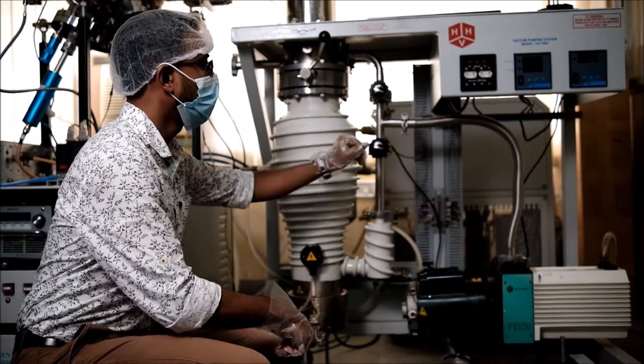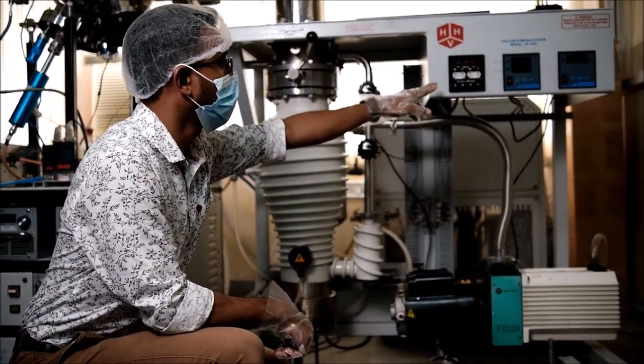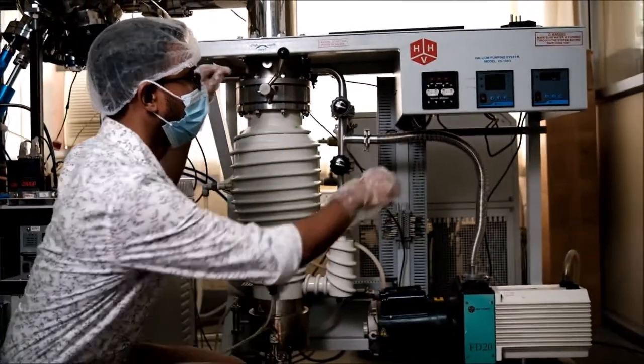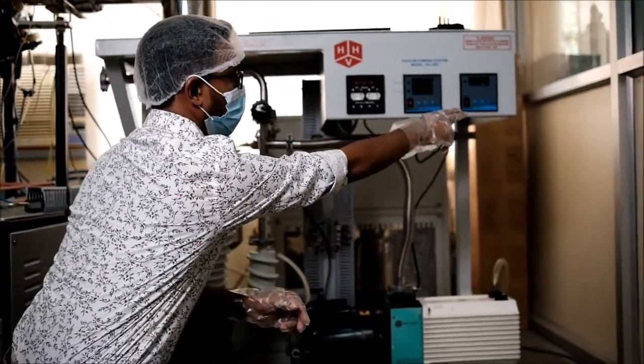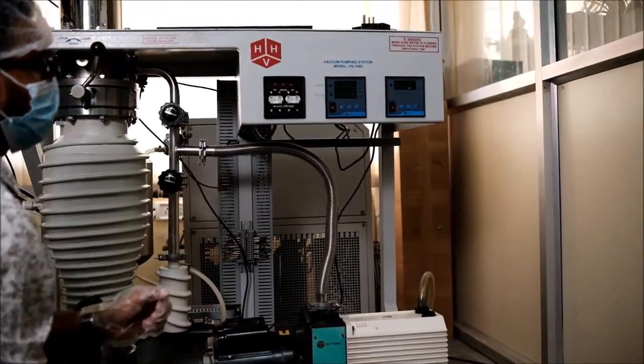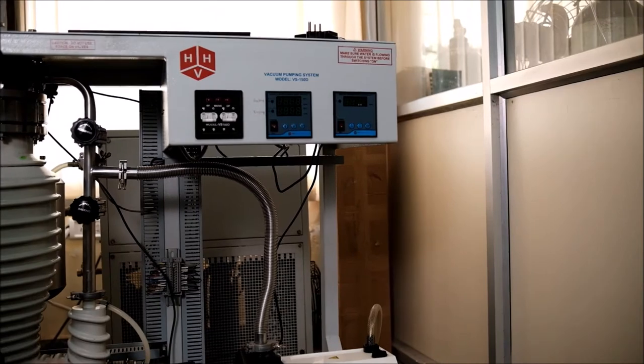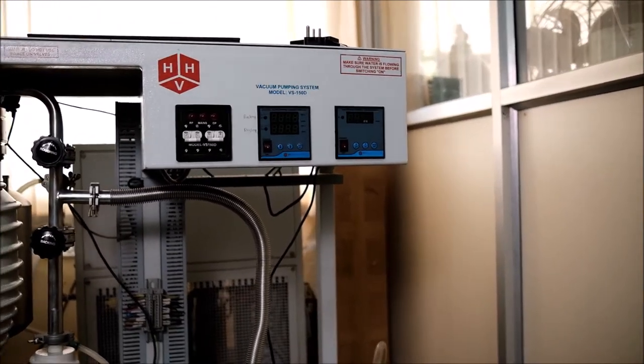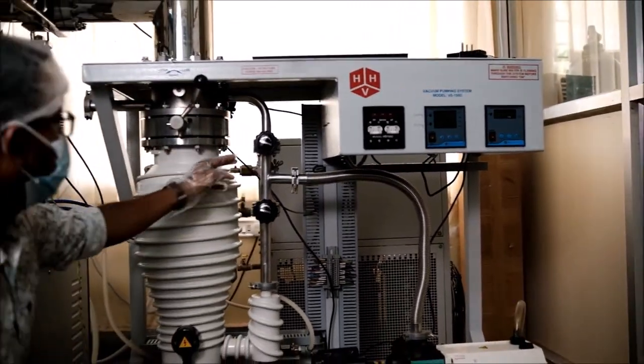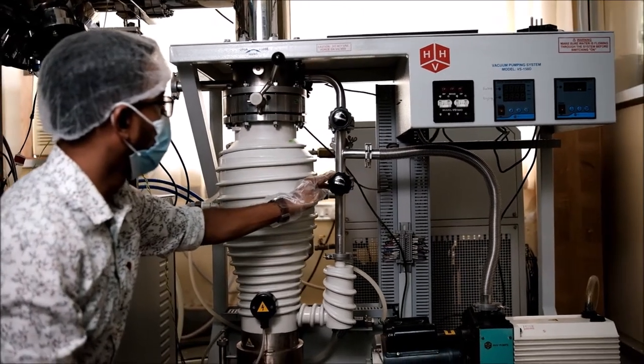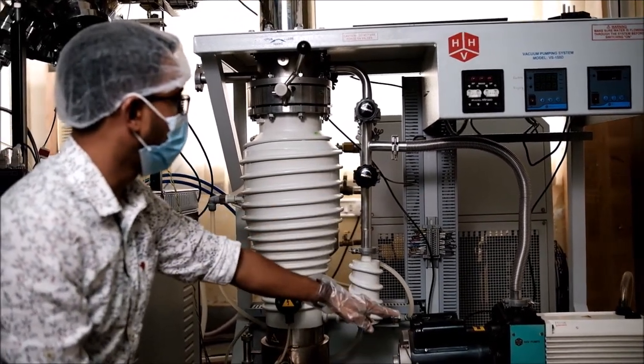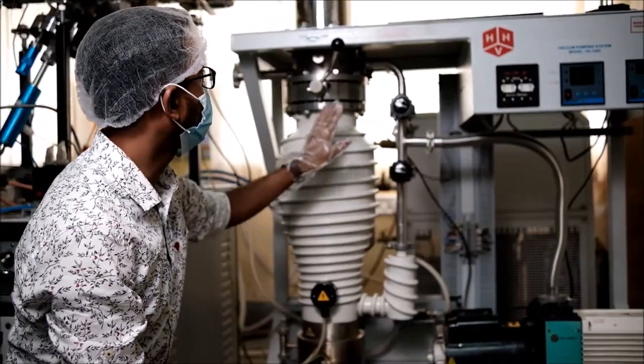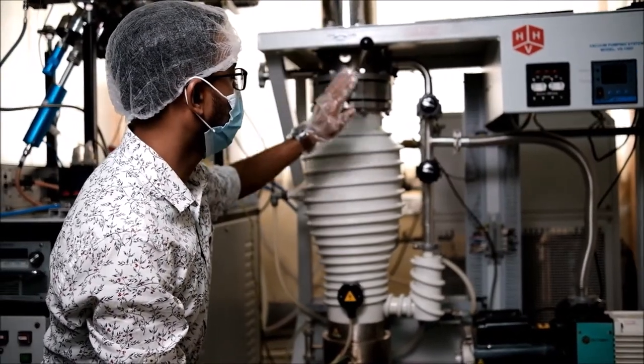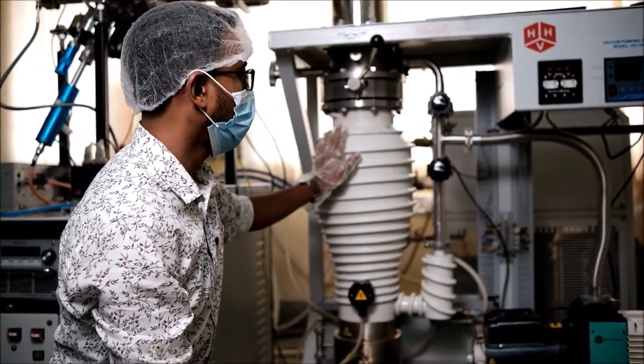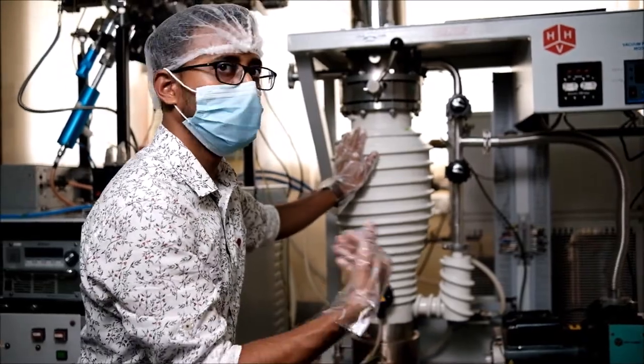And these are the two switches for the rotary pump and diffusion pump, and these two are the display units to show the pressure from the Penning and Pirani gauge. And through this butterfly valve we connect the rotary pump to the diffusion pump or to the chamber whenever we require to. We will show you how this is maintained while we show the actual deposition.